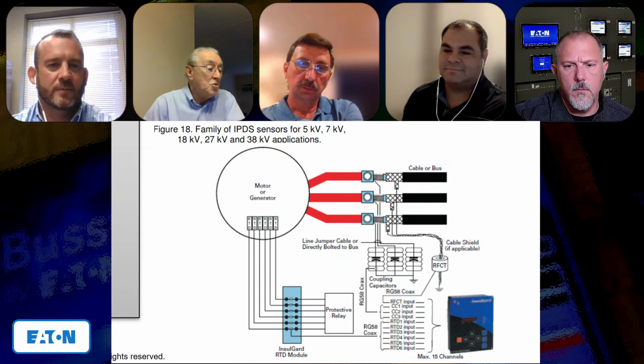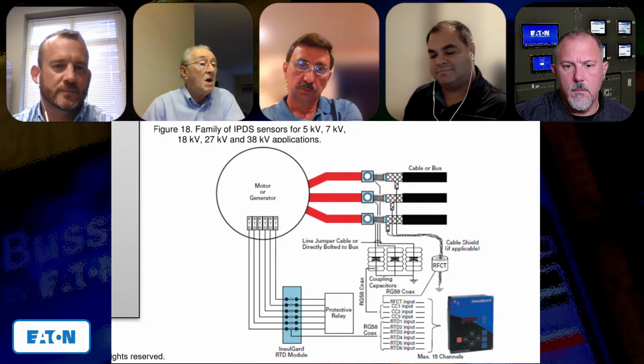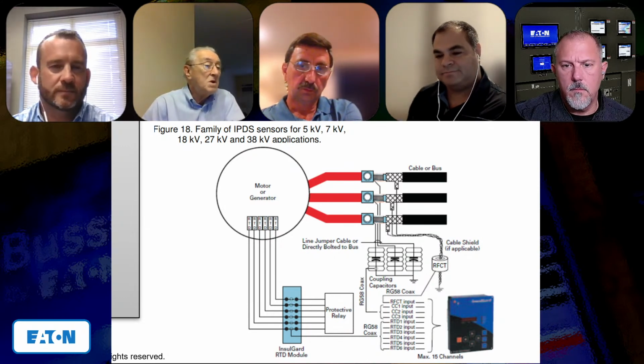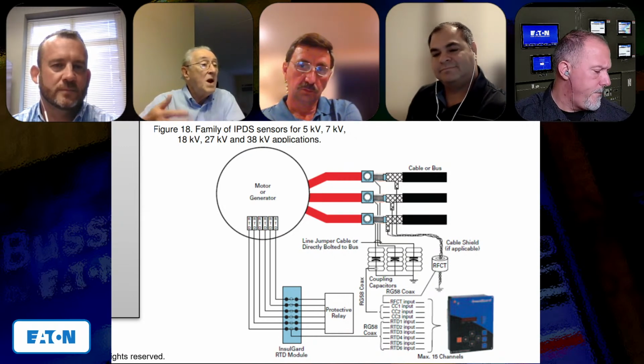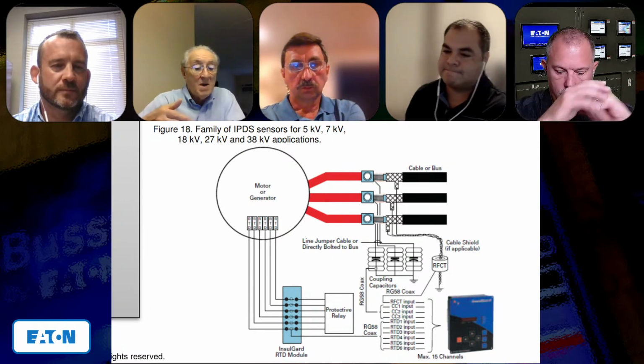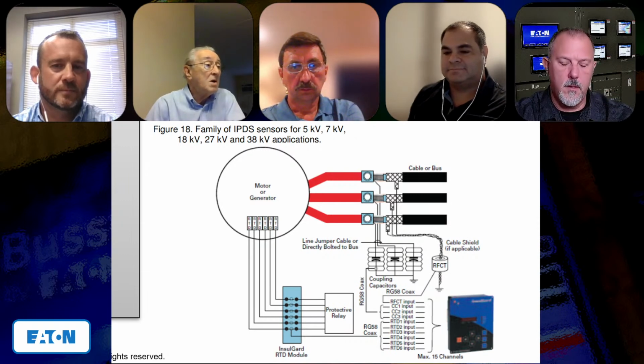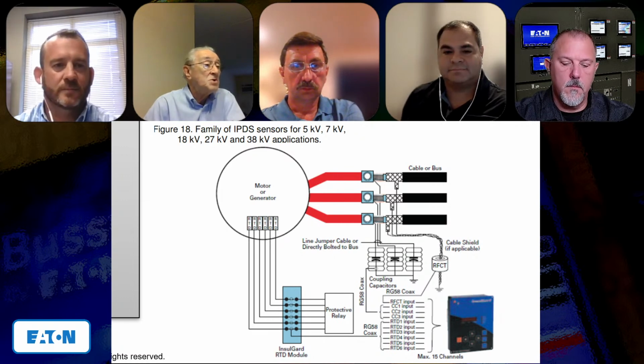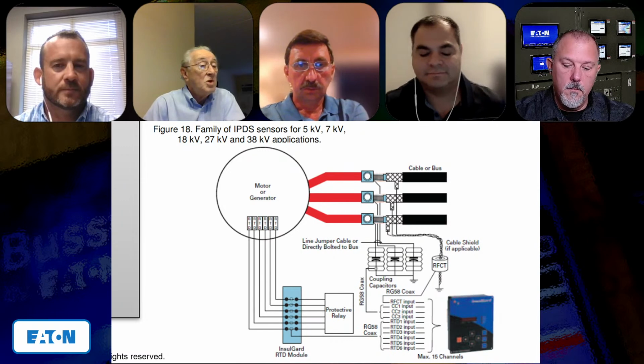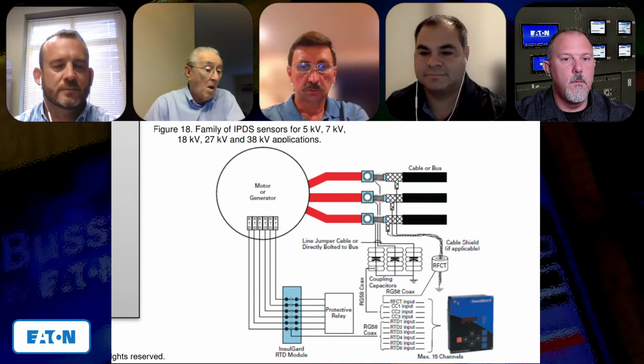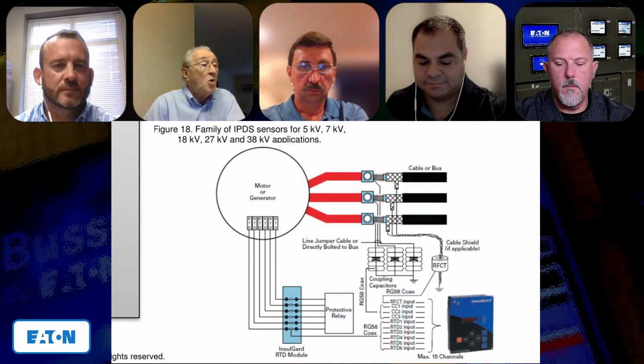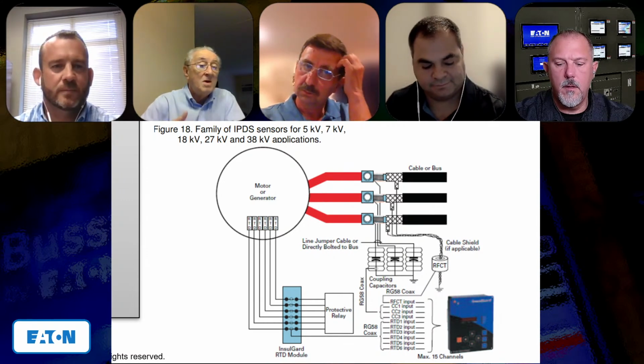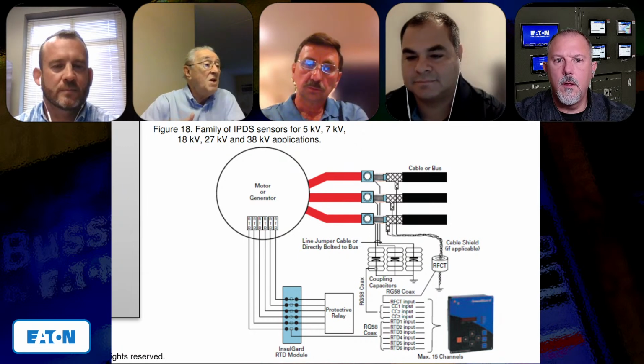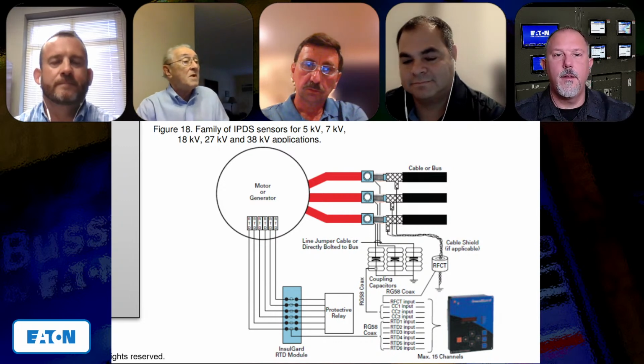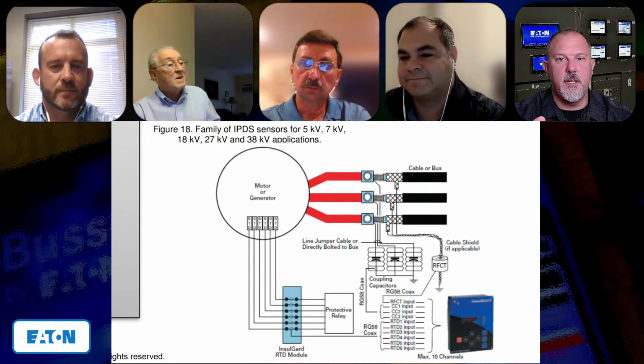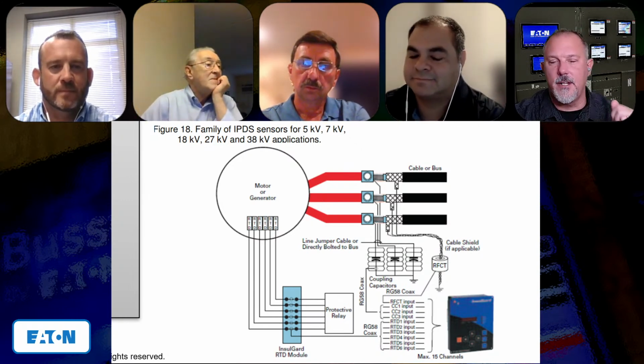A relay usually should control some device, and if the measured parameter exceeds some threshold, the relay should operate and change the mode of the device's work. Our InsulGard, a partial discharge measurement instrument, is diagnostic. And unfortunately, there are no defined thresholds to say that it is necessary to immediately stop the device. Okay. So this is more of a monitoring system that sends a flag up that tells you, hey, you've got to look at this. It doesn't necessarily trip something.